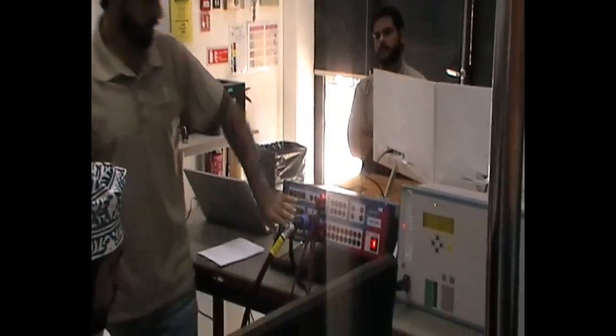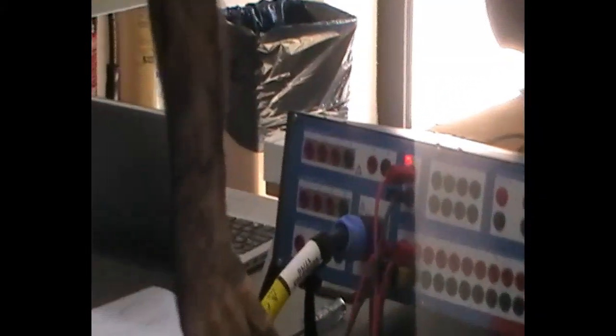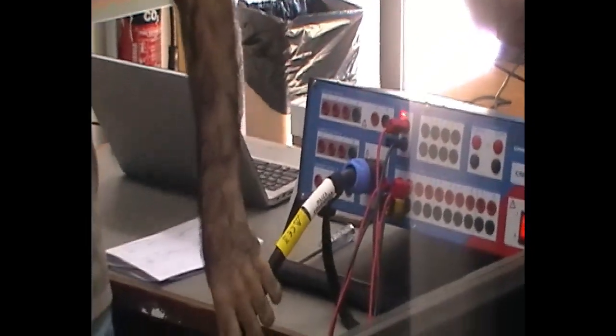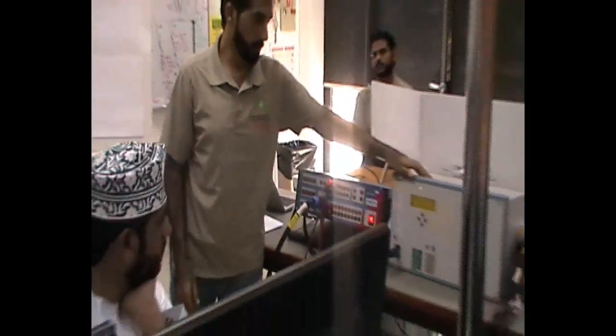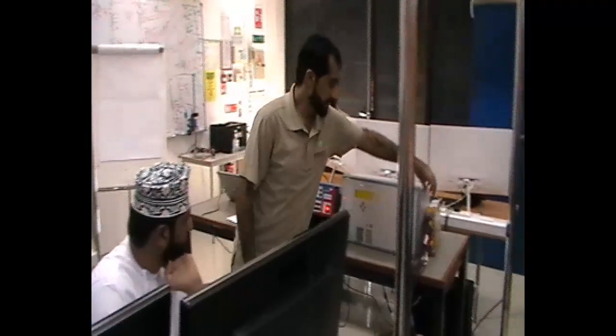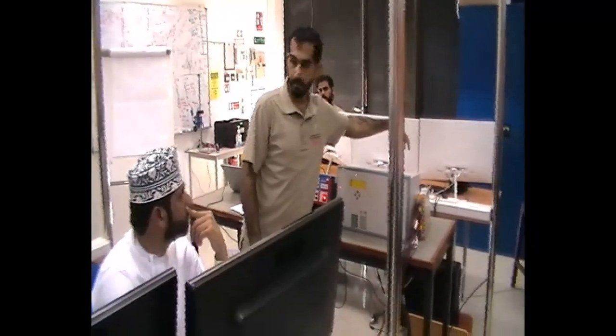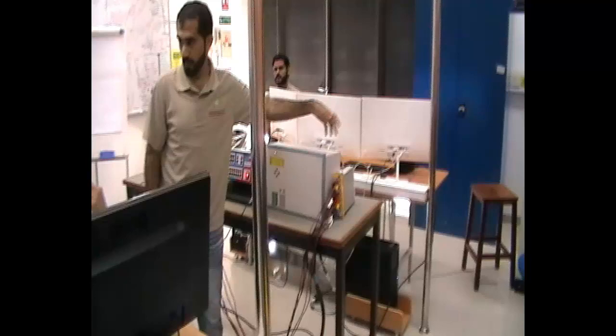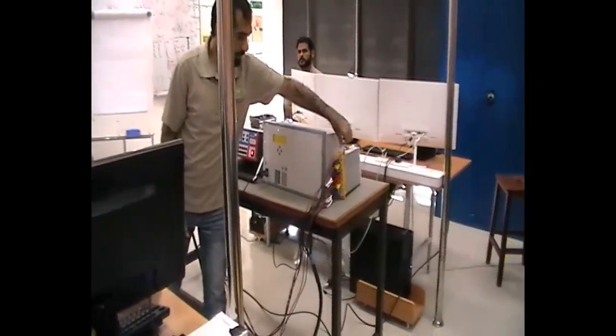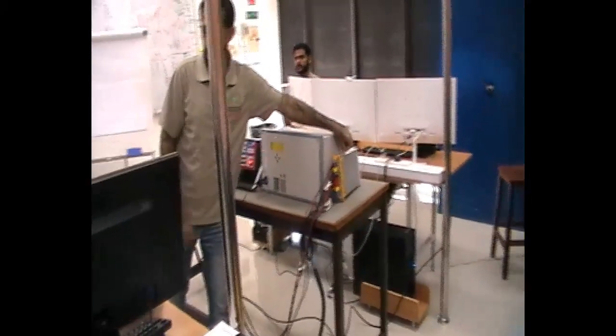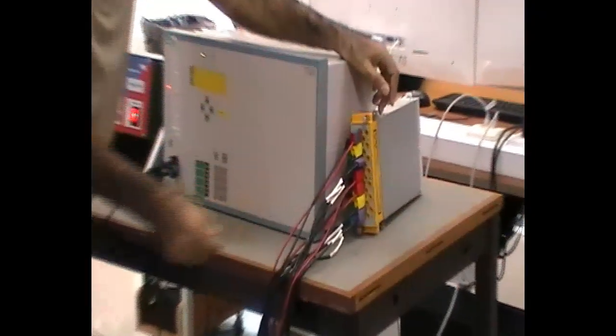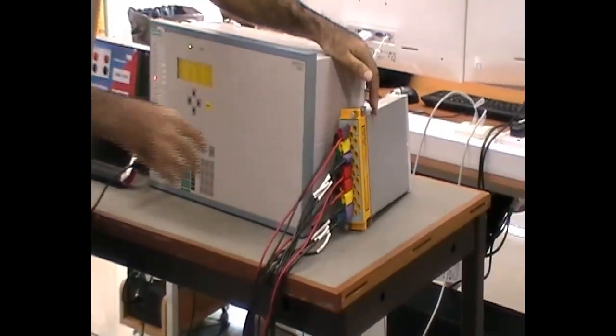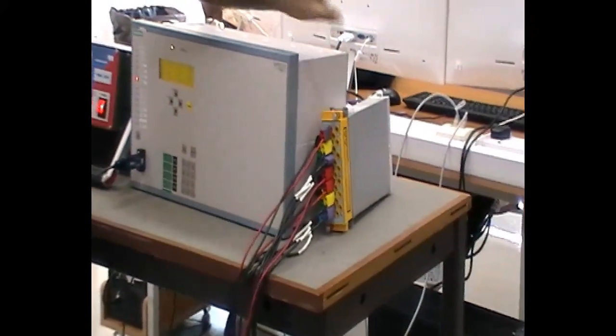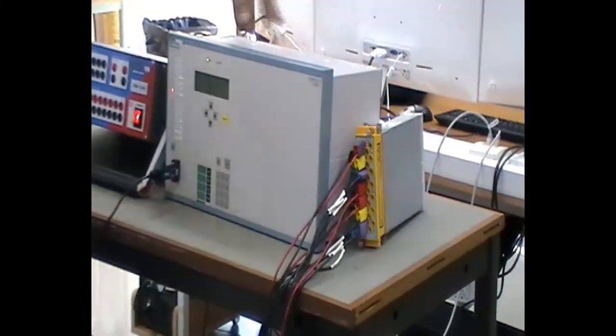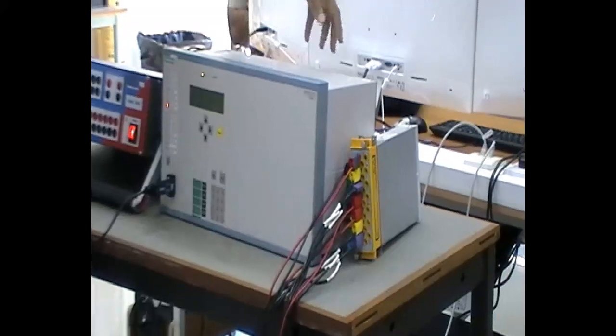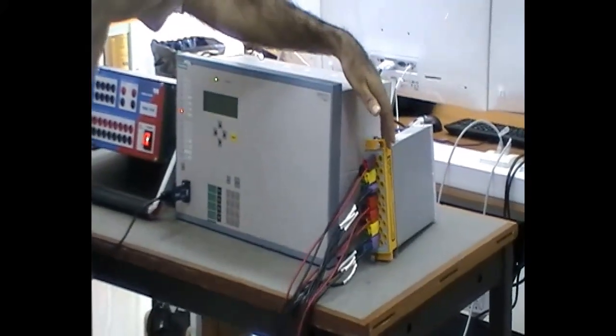The last one is the injection. I have here 3 sets of current and 3 sets of voltage: ABC, or red, yellow, blue. It goes into the test kit. I could have connected it directly to the relay, but it would take time, and for simplicity we use what we call a test block. The one which we inserted here is a test block. At the end of this test, maybe I'll remove it just to show you how it works. So in the substation, I will not work with the connections at the back side of the relay. I always work at the test block.